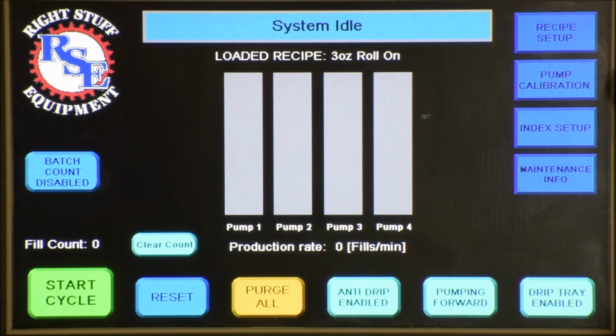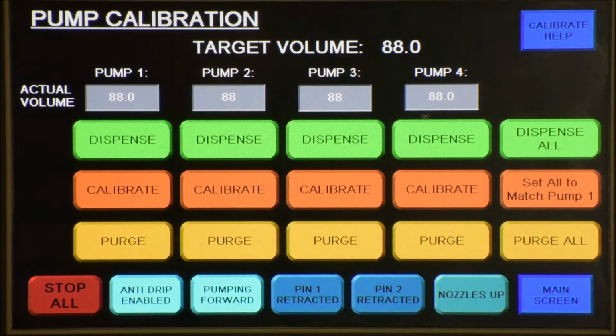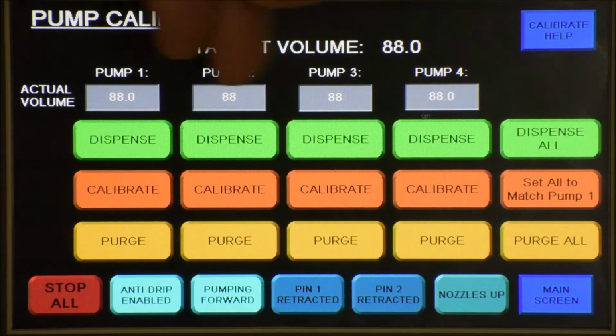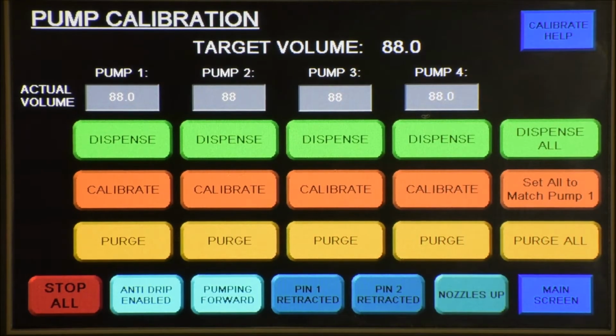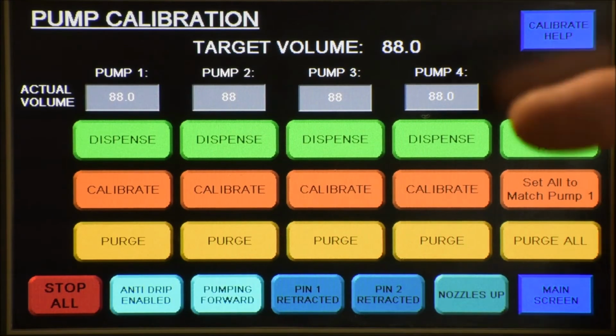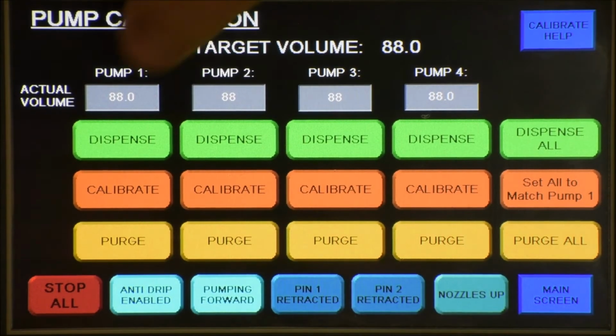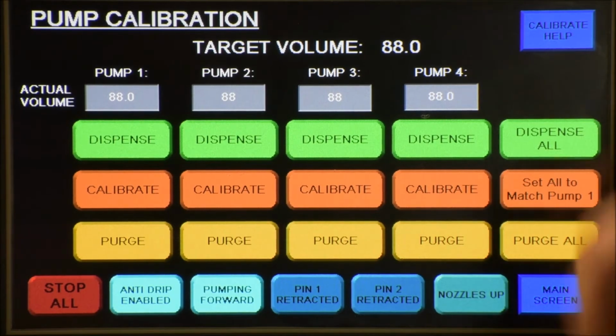So now the next menu down is called pump calibration. We'll go into that menu. So this is where you're going to dial in your fill levels. You've got 4 pumps here. Those represent 1, 2, 3, 4 on the fill set. You can dial in each one individually, or just dial in the first one and set all of them to the same value. It's going to pull your fill volume in milliliters from the recipe that you selected. So we've got an 88 milliliter fill selected right here. And to calibrate this, what you're going to do is put a bottle under fill valve 1, hit this dispense button, which I'll do off screen here.